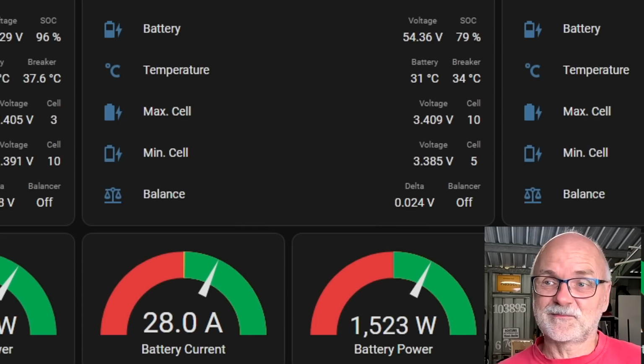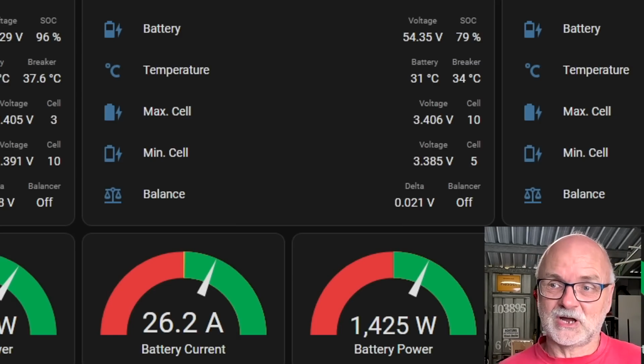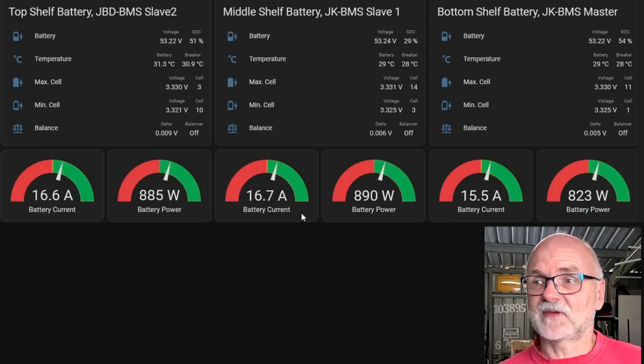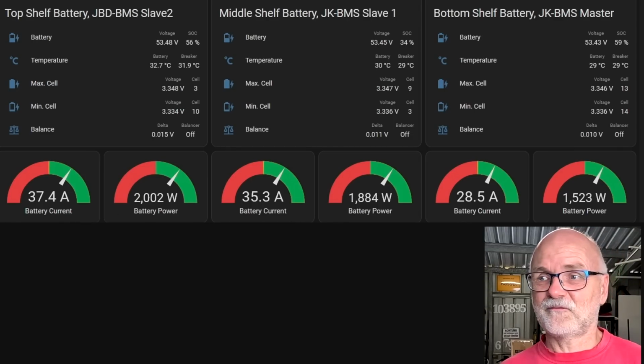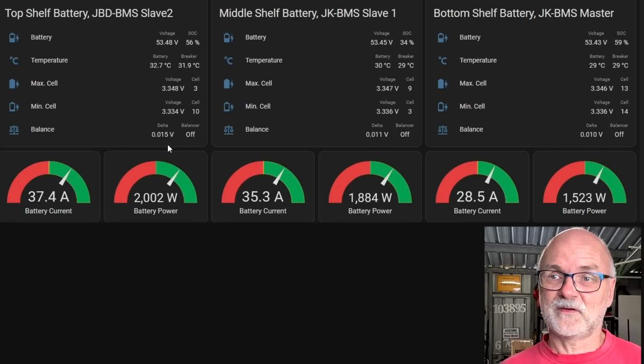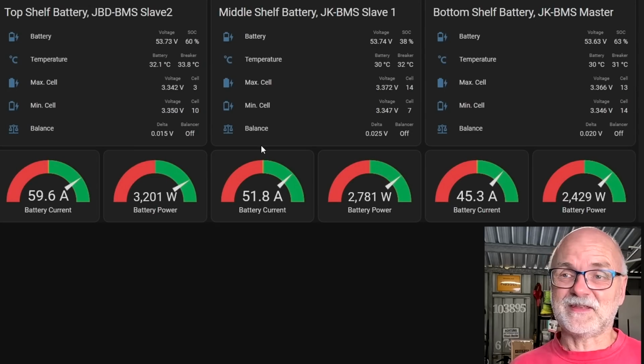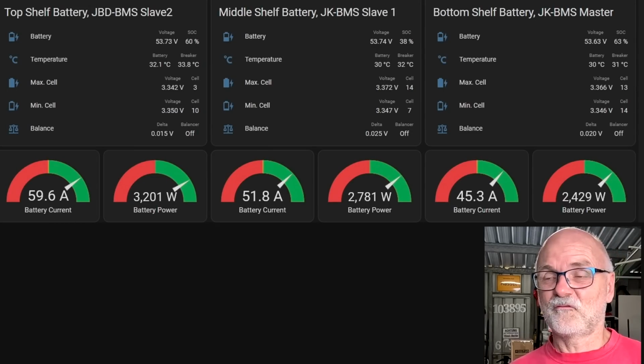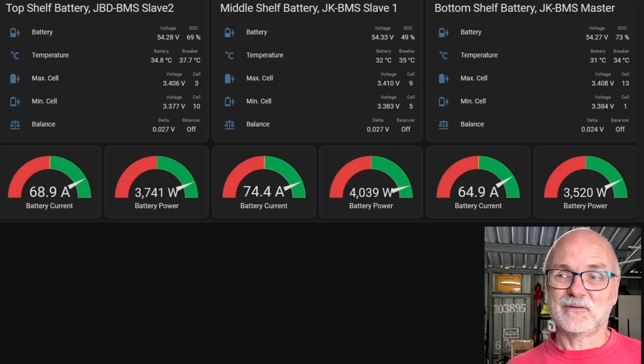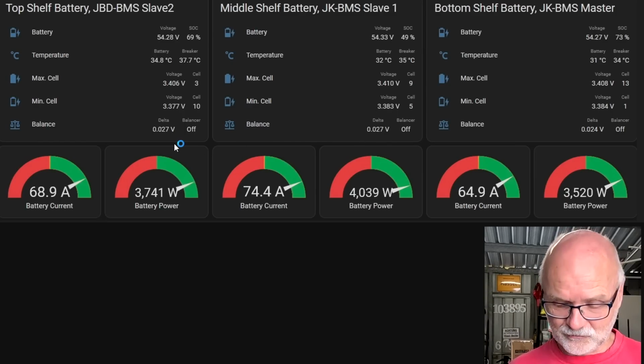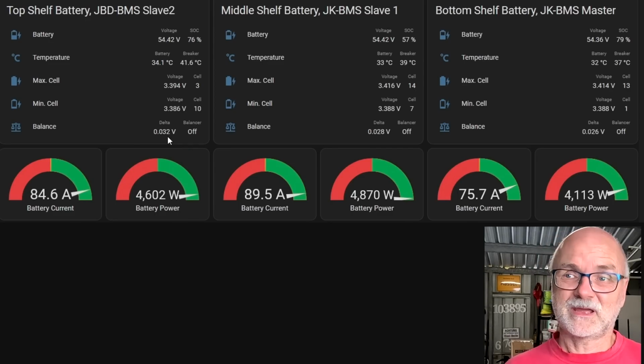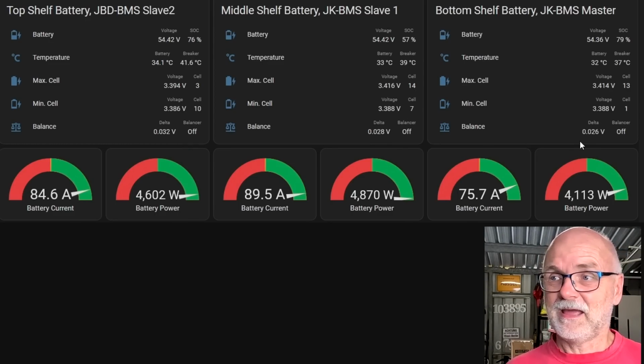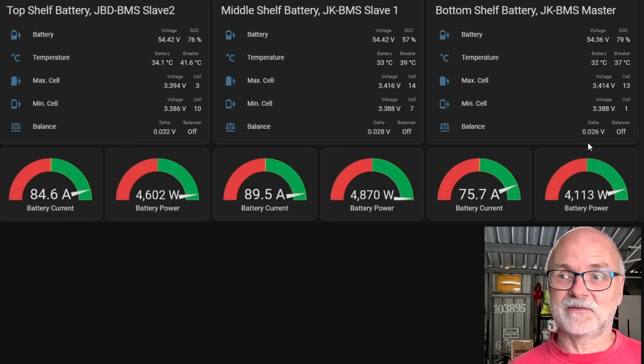I made a couple of screenshots this morning to show the behavior of the middle shelf battery while charging at different currents. At 16 amps: 16.7, 15.4, deviation 6 millivolts. Around 35 amps: 37, 35, 28, again 11 millivolt deviation, up to 15 millivolt in the top battery, but everything is fine. At 50 to 60 amps: 59 in the top battery, 51, 45, deviation 25 millivolts. At around 70 amps: 68 in the top battery, 75 in the middle, 64 in the bottom battery, 27 millivolt deviation, same as the top battery. At around 90 amps: 32 millivolt in the top battery, 28 in the middle, 26 in the bottom battery. So it's actually in line with all the other batteries and the current as well — it's not lagging behind anymore.